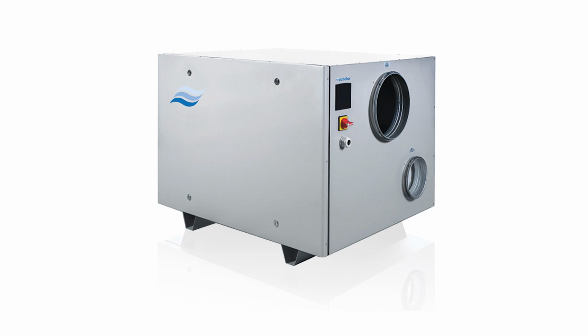Well, desiccant dehumidifiers can be placed in series, one after another, with cooling or heating modules to meet an exact temperature and humidity condition. This means that they can deliver humidity control potentially as low as 1% RH and sometimes even lower. This is unachievable with a condensing technology as it's limited by the cooling core's ability to condense moisture in a liquid state without freezing it. Well, desiccant systems are sounding like the more flexible solution, Dave.